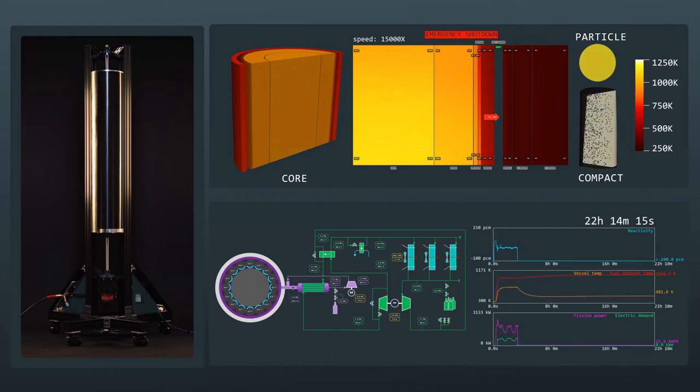A small amount of decay heat is still produced by fission products. After the fuel temperature peaks in a few hours, the entire core cools to ambient temperatures. The fuel never exceeds 950 degrees, well below the 1600 degree limit established by TRISO fuel qualification.